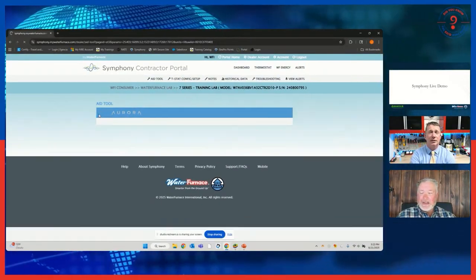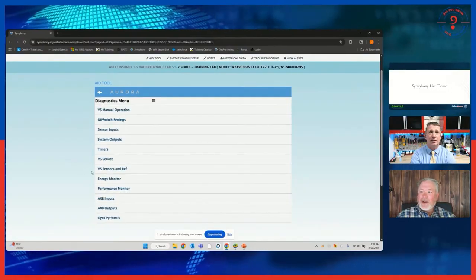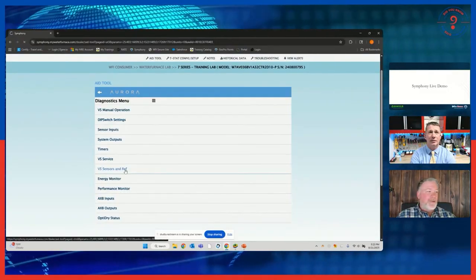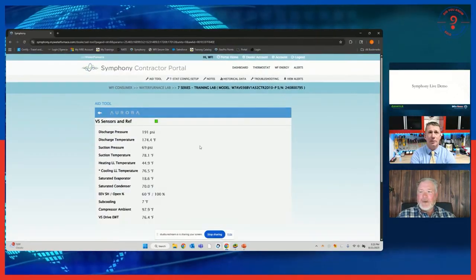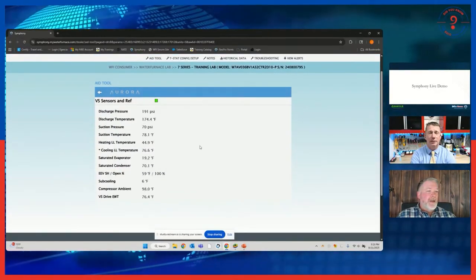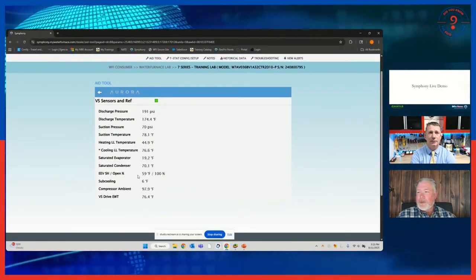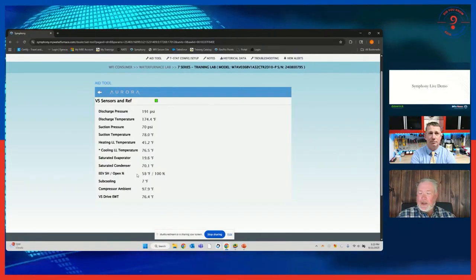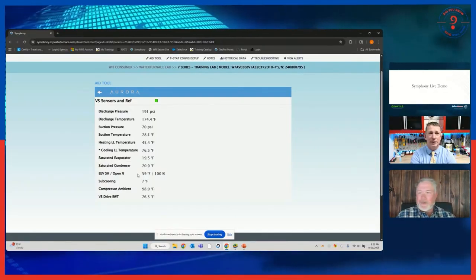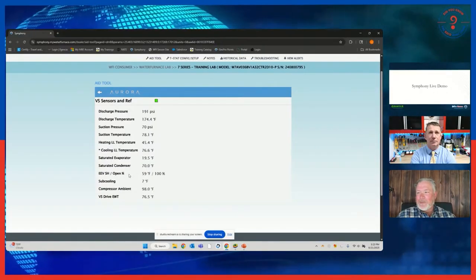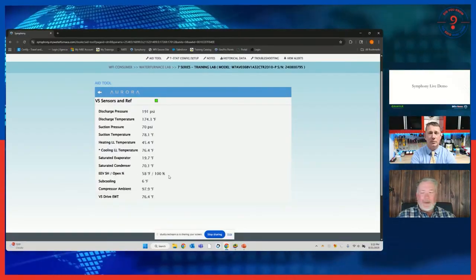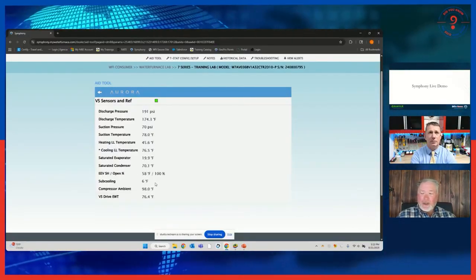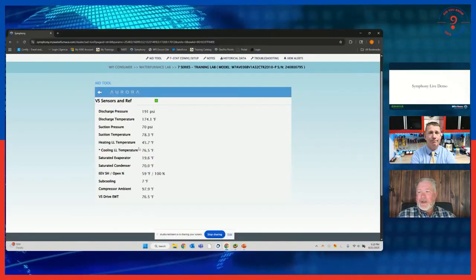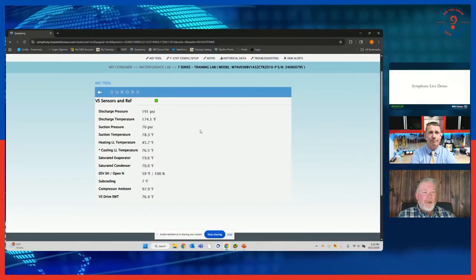In the diagnostics, if I want to see things broken down, I can go to sensors and refrigerant and look at them individually — all my pressures and temperatures. This chart shows my EEV superheat, and since I just shut the unit down, it's changing now. There's my percent open on the EEV, my subcooling, compressor ambient temperatures — everything I need is right there.